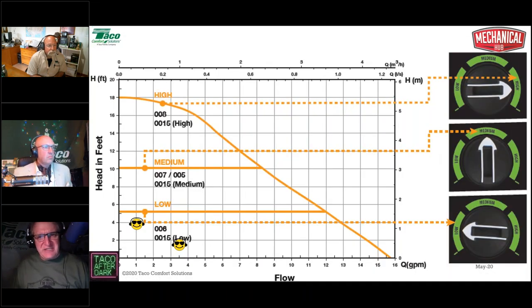This is the 0015E3, Taco's 0015E3. It's a three-setting circulator. The low setting is 5 feet of head, the medium setting is 10 feet of head, and the high setting is full speed, fixed speed. In the low and the medium, both are ultimate flat curve pumps. From here to here, or from here to here, the pump will vary its speed in order to maintain that fixed pressure differential. We showed you an illustration of how that works last week, but let's take a look at our 7 gallons a minute, 5 foot of head system.